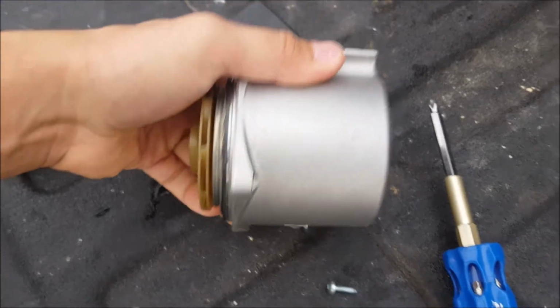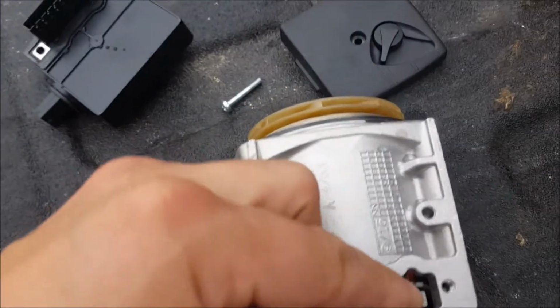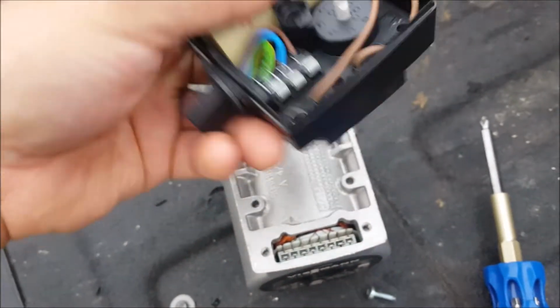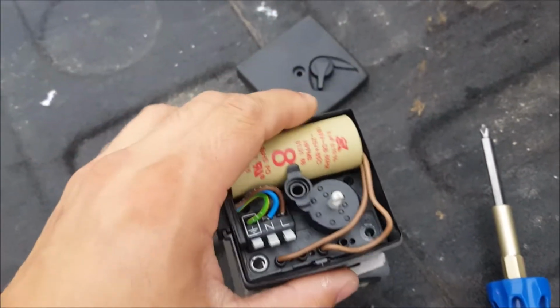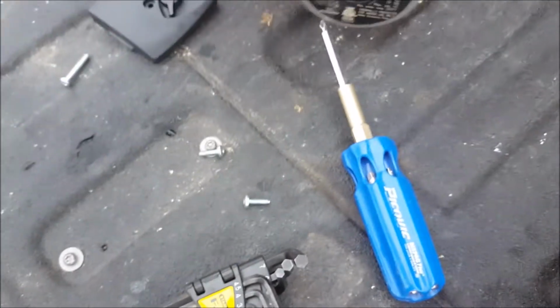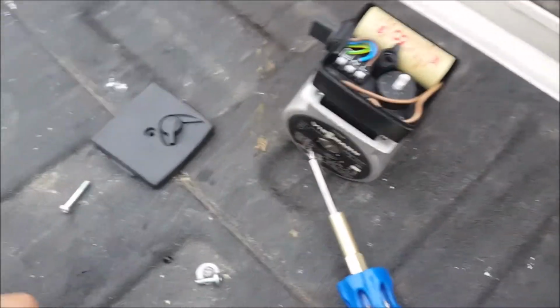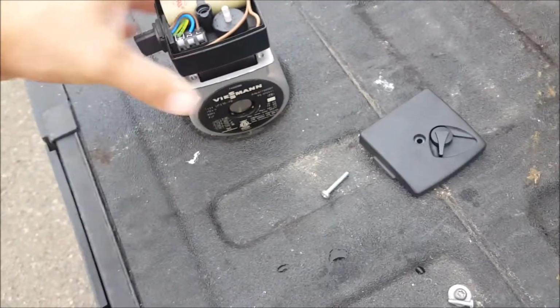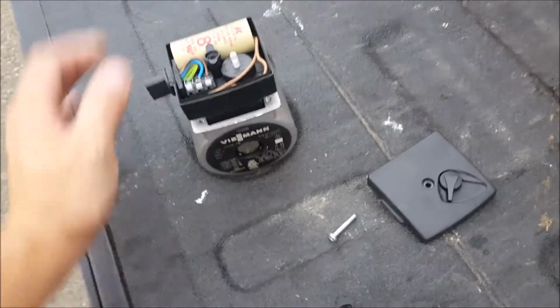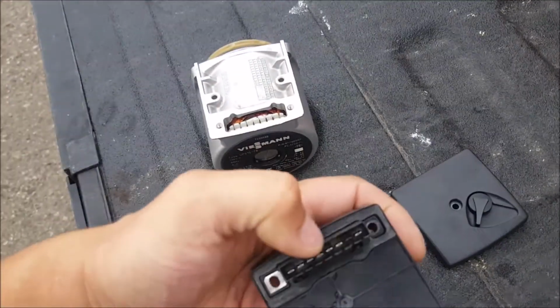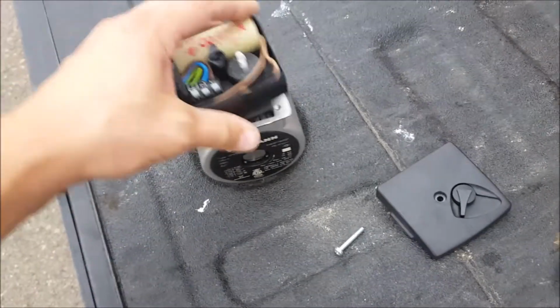So what we did is we cleaned that up a little bit and closed this up with a little screwdriver. So there's the problem, the failure mode in this pump. If you have that issue, you can clean the contacts, try to get a little better pin fitment if the pin's not totally burned out, or maybe you can just replace this head or figure something out. Unfortunately on these Combi Plus units, this is a proprietary pump and you can't find it anywhere except from Viessmann. So we were going to be 4 or 5 days without heat or hot water until we found this and were able to make it limp through.